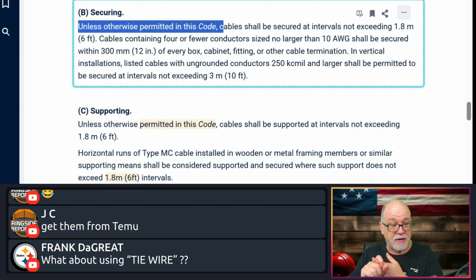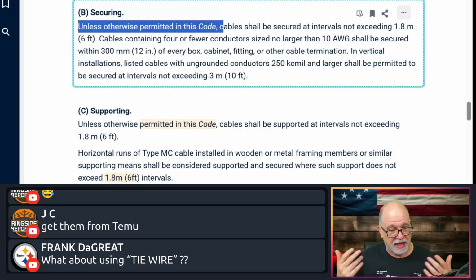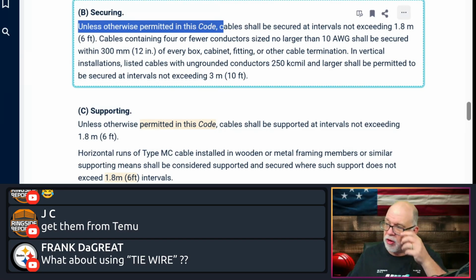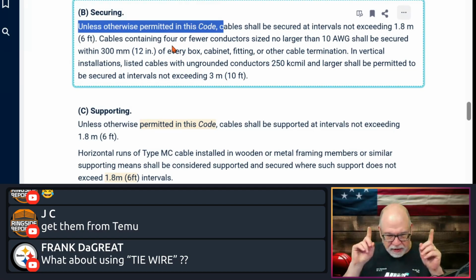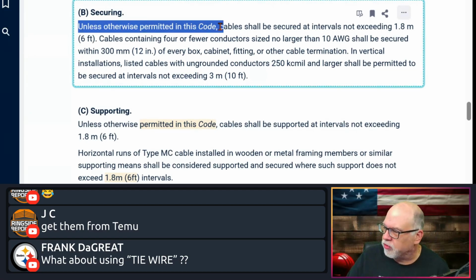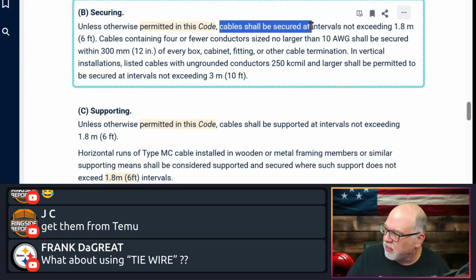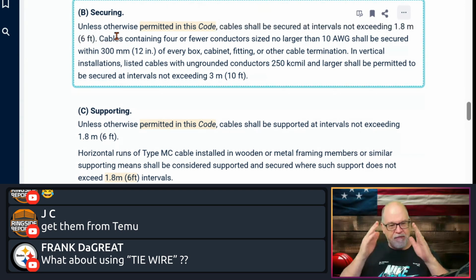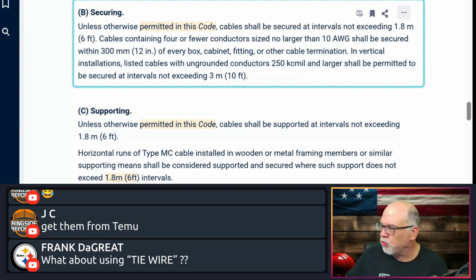5, 6, and 7 modify or supplement chapters 1 through 7 where applicable, meaning they can change the general rule, right? And then, of course, you have chapter 8, which is a standalone, okay, communications and things like that. So it's saying, unless permitted otherwise, here are the rules. It says cables shall be secured in intervals not exceeding 6 feet. Okay, so every 6 feet, you're going to secure that MC cable.